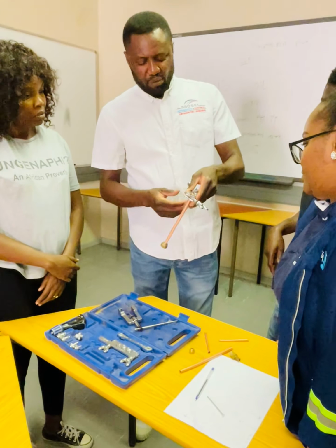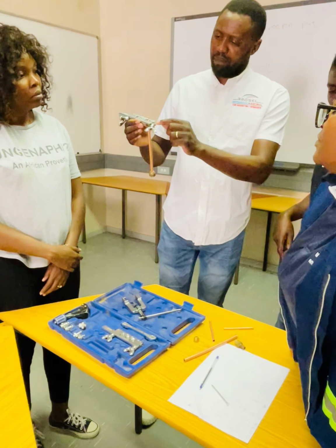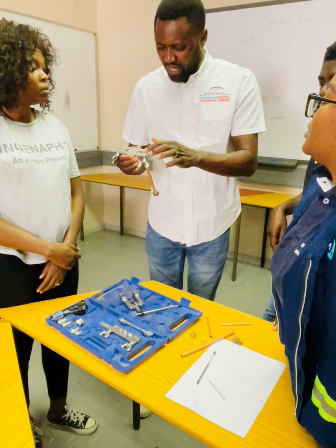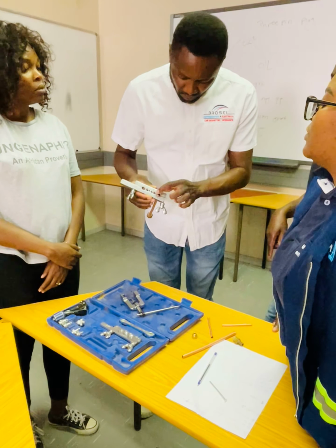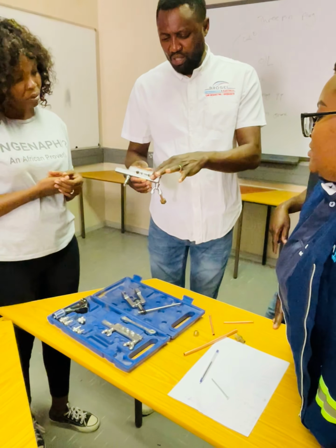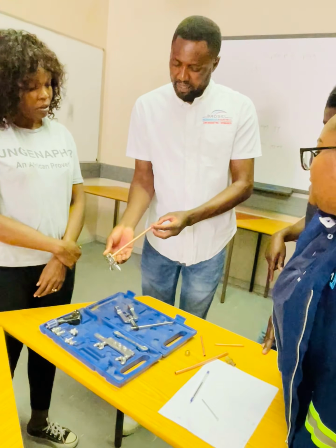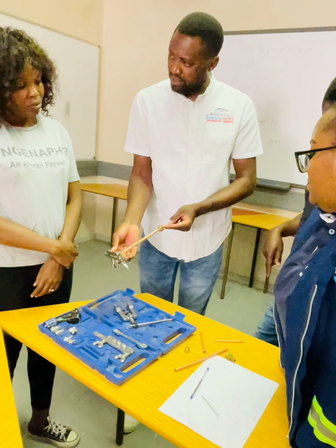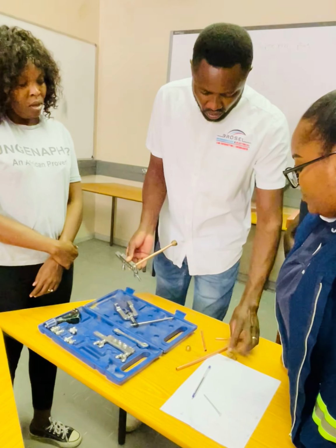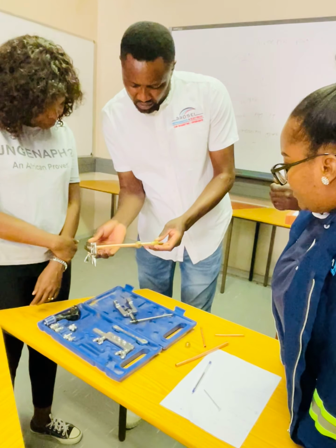You put it up here. We don't really use any type of measurement. I always make sure I put up my pipe an inch over, so that when I'm going to flare, it should be able to sit within this area here, the chamfer. If you make it a bit longer, then it's going to be over, it won't fit in the nut, and it will touch the thread. It doesn't need to touch the thread, otherwise it's going to leak. It's not going to sit on the valve. By the end, when you are done, you should be able to sit properly on the valve.